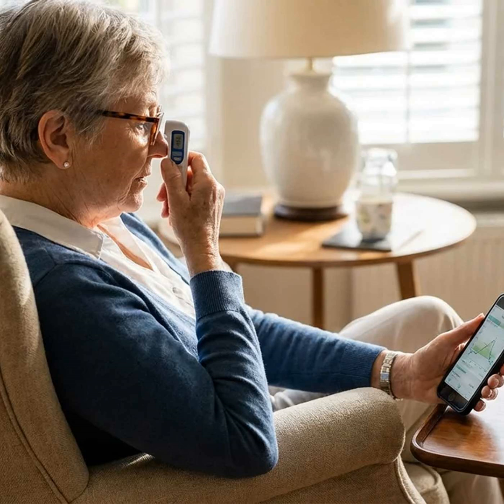No numbing drops are needed. The probe impact is so quick, it's usually painless. The iCare Home has adjustable forehead and cheek rests to help the patient hold it in the right position, and lights on the probe base that show green when alignment is correct. The patient pushes a button when the device is aligned, which triggers 6 quick readings. The final IOP is the average of those readings, dropping the highest and lowest of the 6.